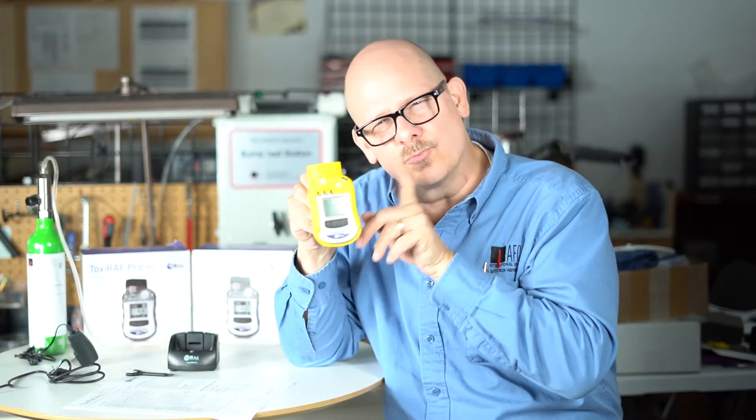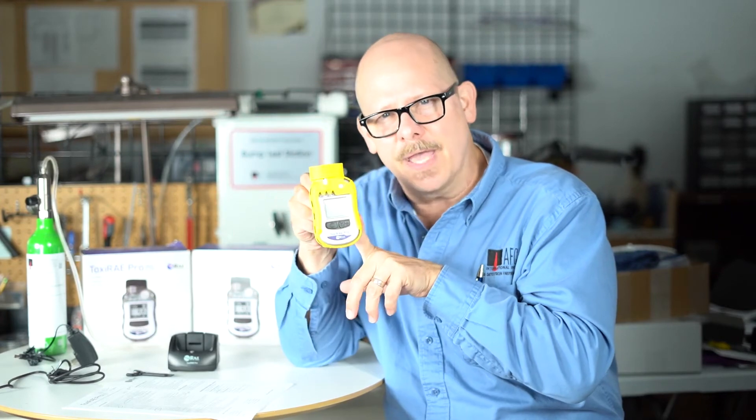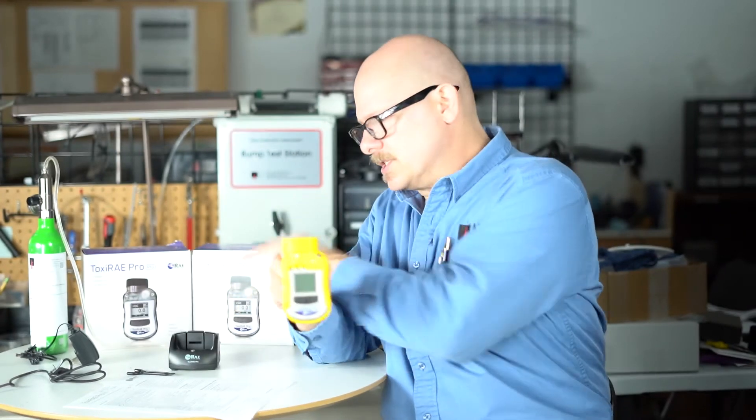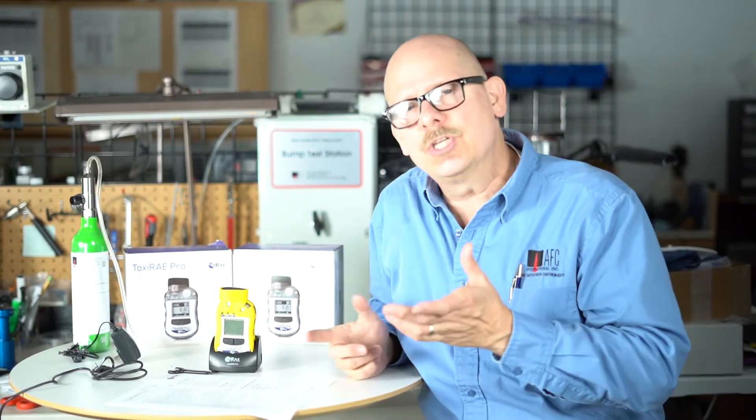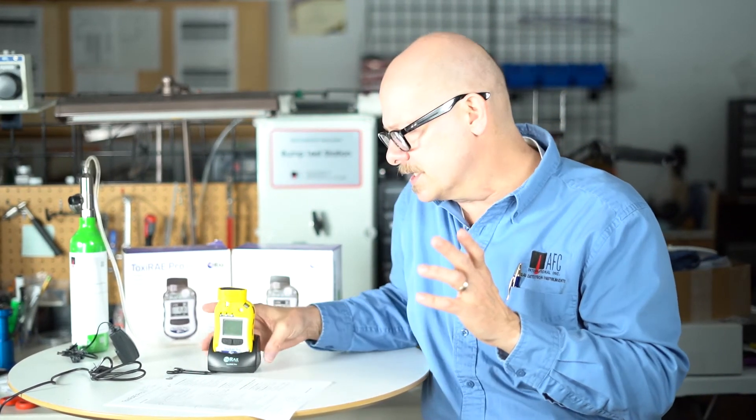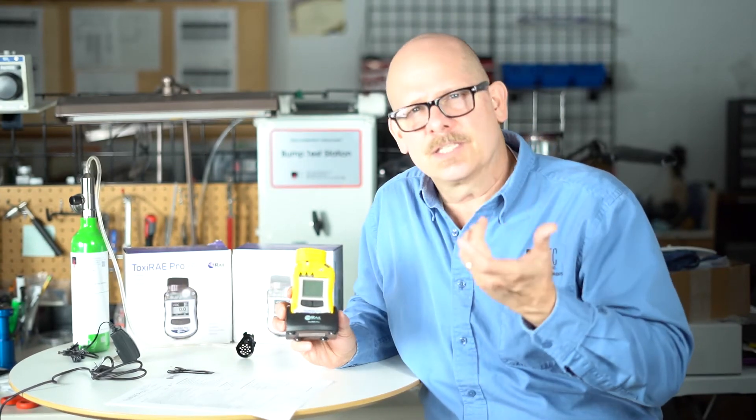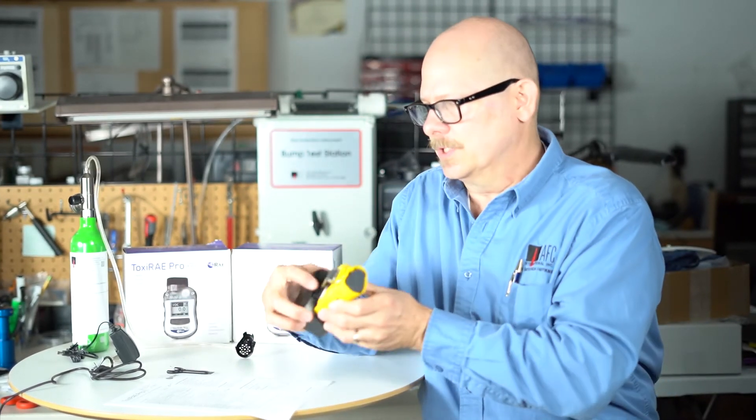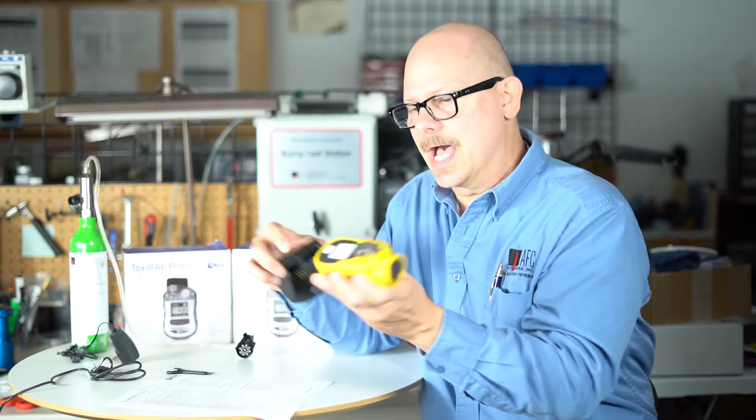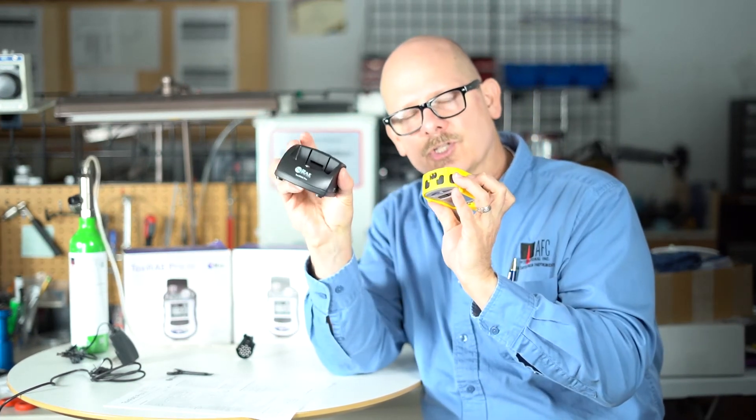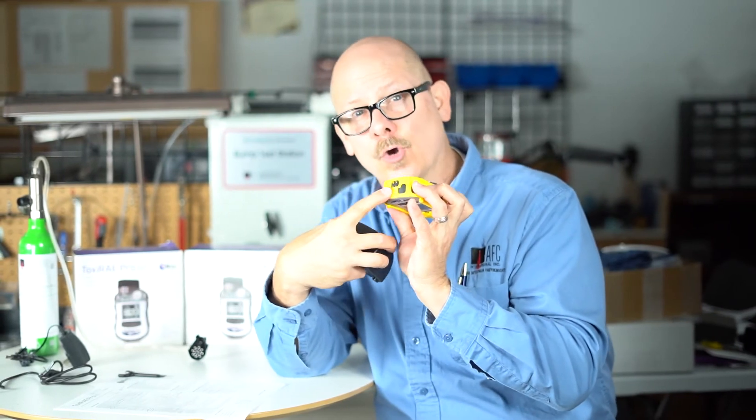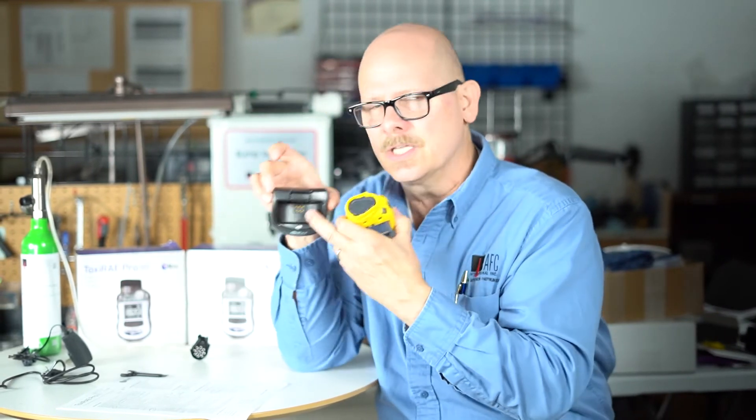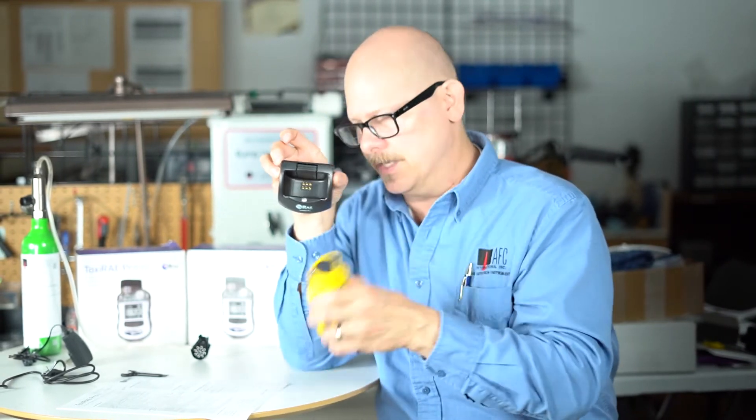It's about 12 hours on its run time on its lithium-ion battery. It is a rechargeable system. It comes with this cradle. We put the unit in the cradle, and that's going to do the charging for you. It will recharge a completely dead battery system in less than four hours. We also communicate using this cradle. This is where the contacts are for dumping our data and also for programming our instrument through the bottom base of the charger.